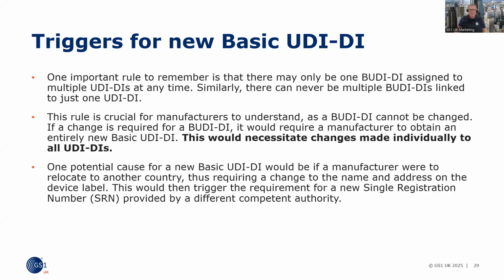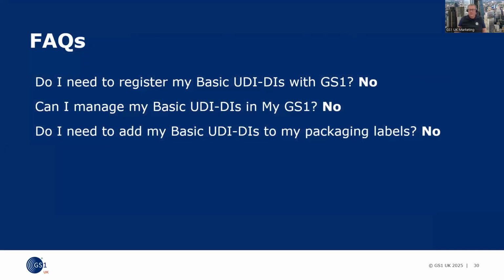Okay, so I'm not going to go into too much detail about that. I'll let you read that for yourselves and look at the links. But some FAQs from, I think this is probably the 25th time I've done this, and we still get lots of people joining, which I'm glad to say. Do I need to register my basic UDI-DIs with GS1? No, you don't.